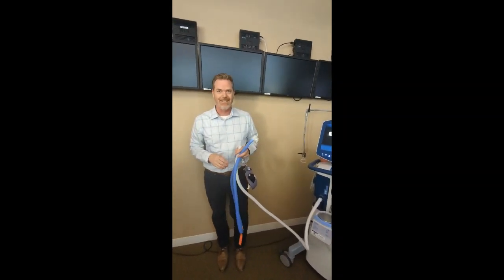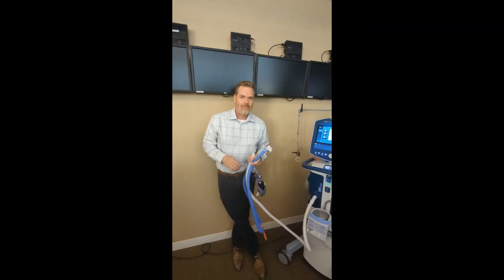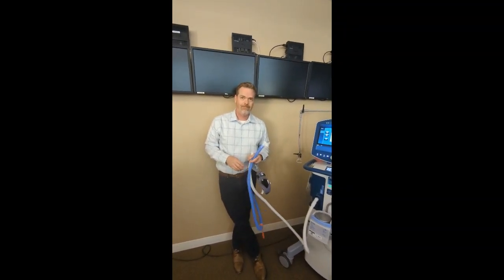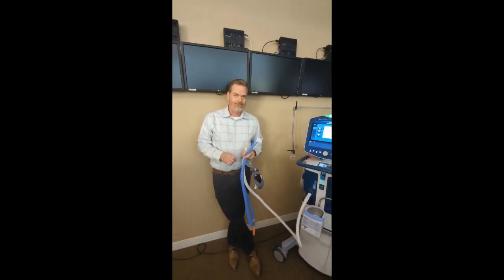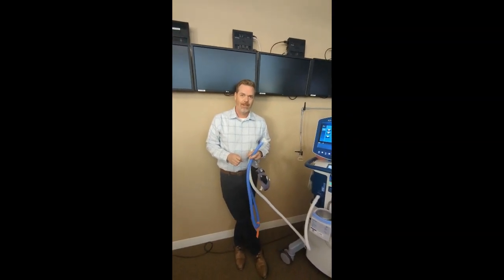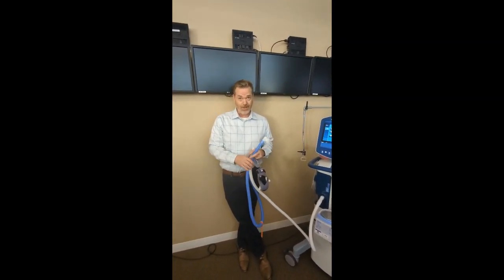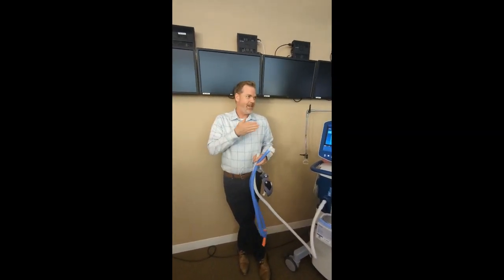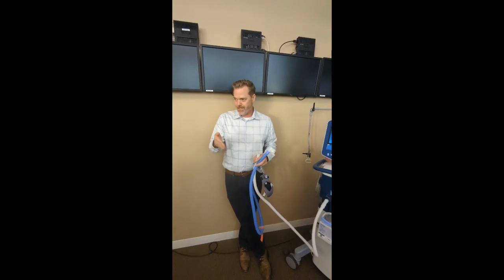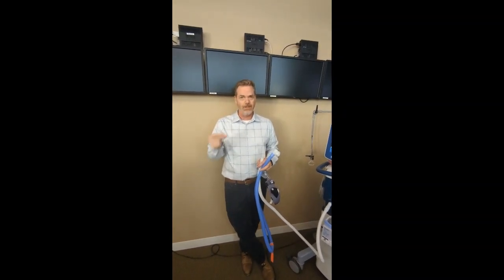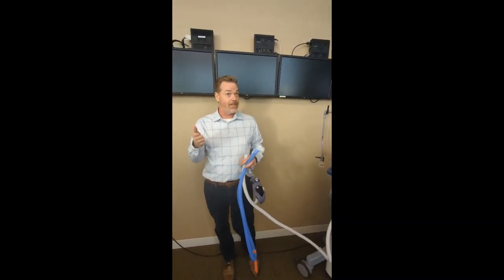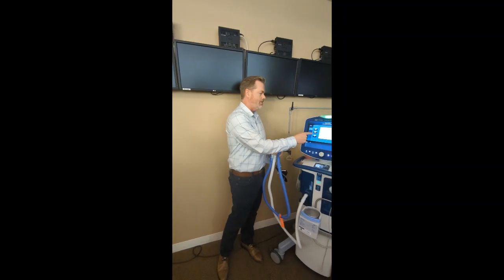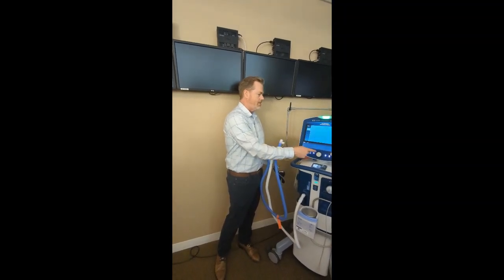Otherwise, you do end up getting a lot of false triggers, a lot of stutters, a lot of things like that. I think that's the one that I forgot to hit. Because I was definitely getting auto trigger when I was playing with it on myself before. So I had the same issue when I play with it. Like even on exhalation, it was trying to trigger. So I think just every little bobble, even your exhalation, if it's in that scenario, you'll get a trigger because that trigger is set very, very sensitive. Invasively, it's great, but non-invasively, it changes those flow characteristics. So that's one thing to see. Let's try this again.